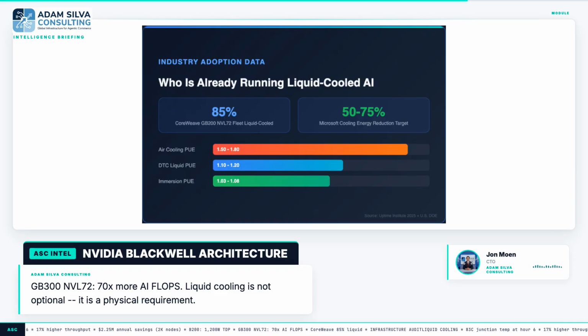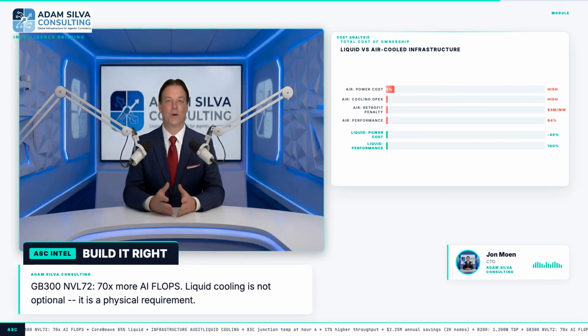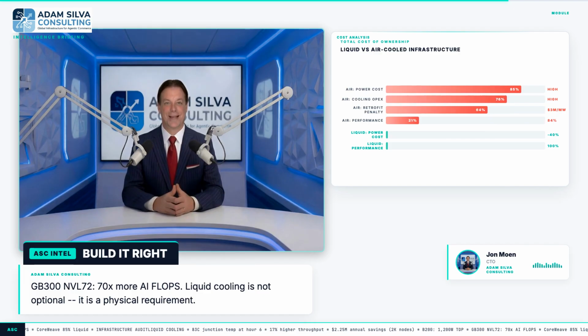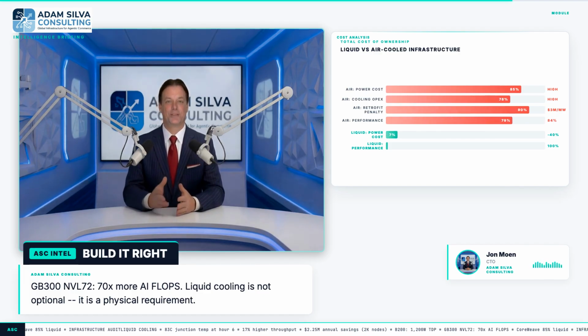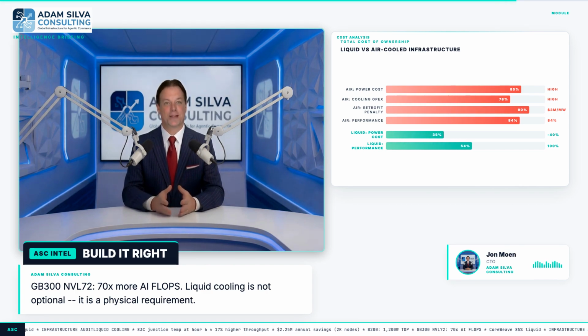CoreWeave is the clearest data point in the market. 85% of their NVIDIA GB200 NVL72 clusters are liquid cooled. Only 15% of their AI compute fleet remains air-cooled. Microsoft is running pilot liquid cooling deployments targeting PUE of 1.1 to 1.2, down from 1.6 to 1.8, projecting 50 to 75% cooling energy savings. The organizations I work with that chose air cooling 2 years ago now face one of 3 paths. Accept the performance ceiling and run throttled workloads. Retrofit at $2 to $3 million per megawatt, or replace the hardware entirely ahead of their planned refresh cycle. All 3 paths are more expensive than spec'ing liquid cooling at initial purchase.